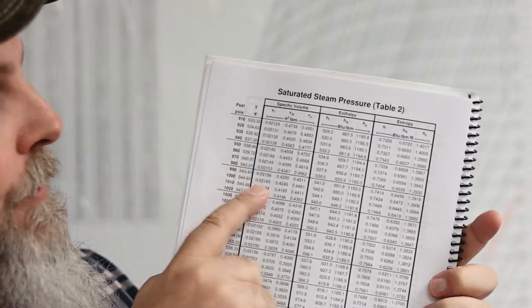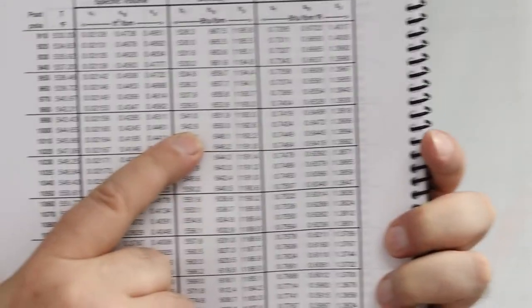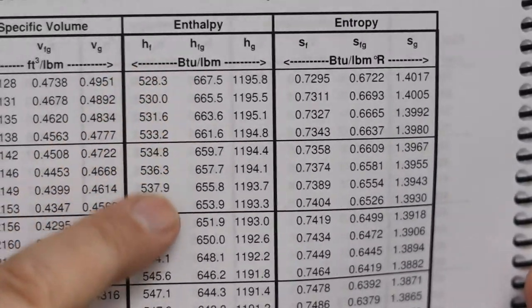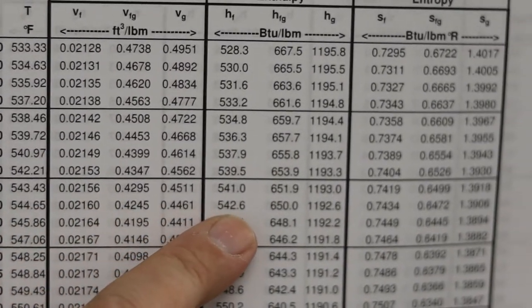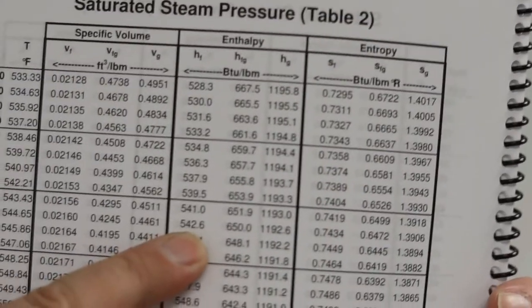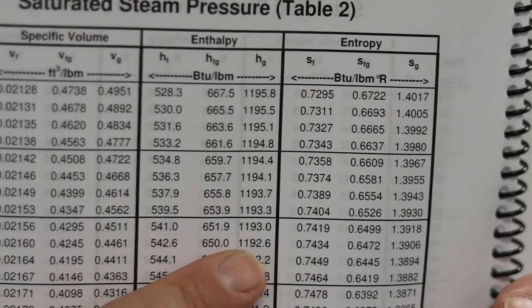Now, if I told you that it was saturated liquid at 1,000 pounds, that means something different, right? That means I haven't gone through that phase change. It's right at the start of the saturation curve, right at the start of that isothermic process, where it will convert to steam. So saturated liquid is a saturated fluid. So if I told you saturated fluid at 1,000 pounds, you would use this first enthalpy, H sub F, for a fluid at 1,000 PSIA. And that is 542.6 BTUs per pound mass. So that's a huge jump. I think Jim and I worked through one of these with you on one of our previous videos.